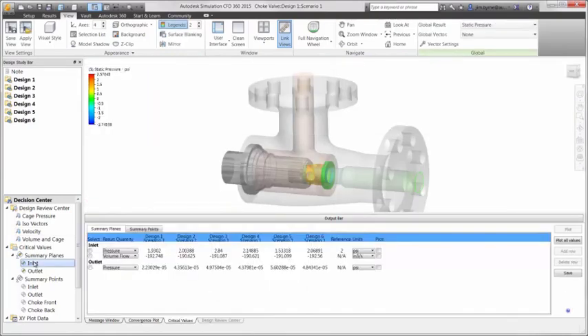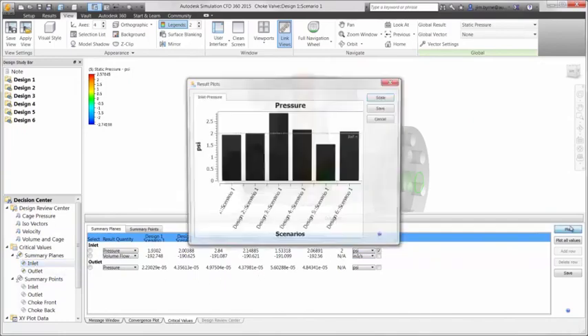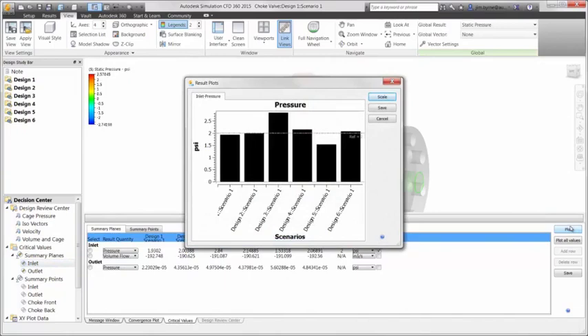Summary information can also be saved from the section planes or point data for comparing maximum values. Taking a look at the values for pressure drop, we can see there are a couple of cage designs that are below our requirement of less than 2 psi. Design 5 is performing the best in this area.